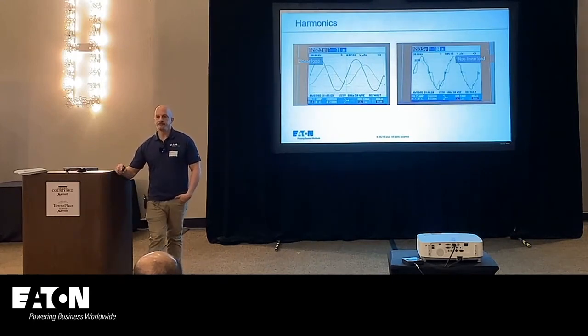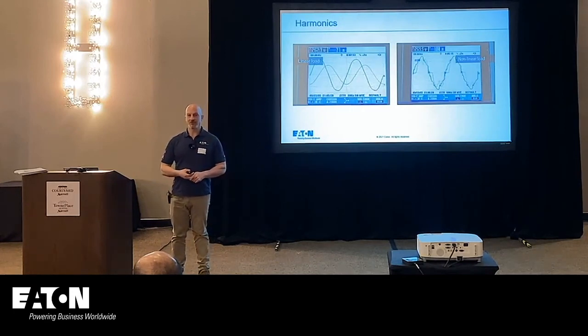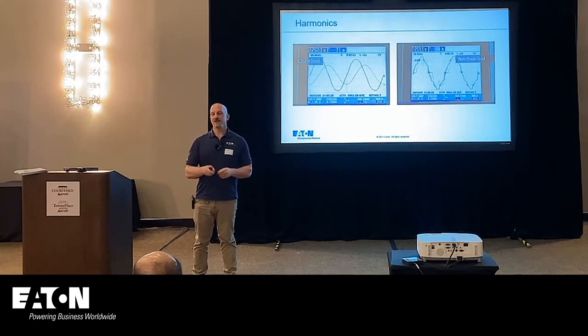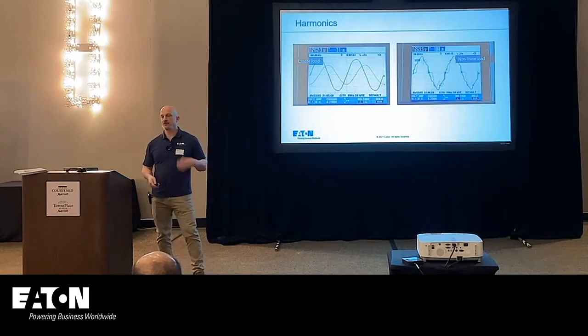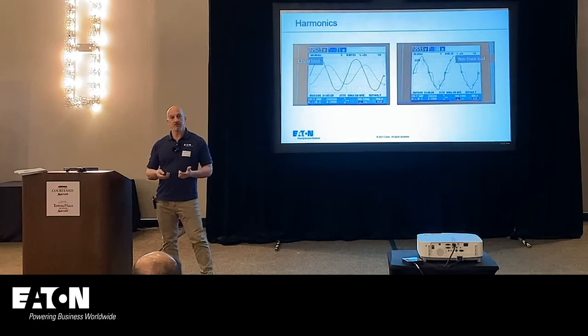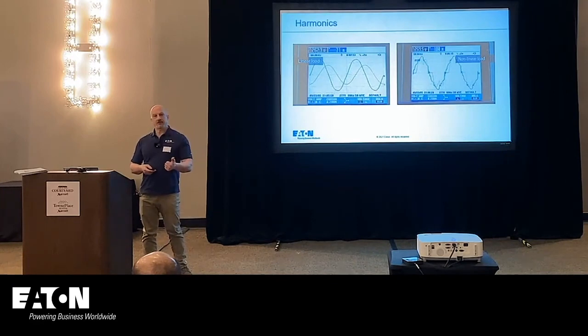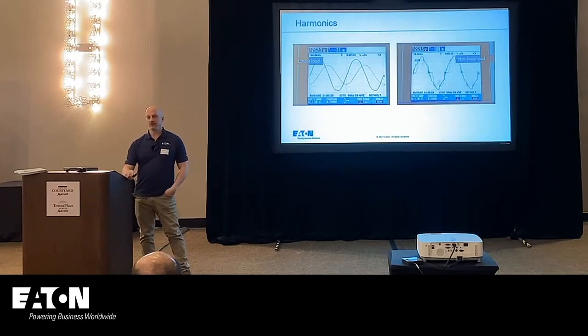But what kind of current is that one, that double hump current? Where does that come from? VFDs. And what type of VFDs, to give you another question, 6 pulse, 12 pulse, 24 pulse? 6 pulse. And what are the harmonics associated with 6 pulse drives? 5 and 7. So you took 6 plus or minus 1, and then 2 times that, 12 plus or minus 1, 11th and 13th. We'll come to that. But harmonics are predictable. That's the good thing. We know they're predictable, and they're characteristic of certain specific loads. So this projector has specific harmonics, drives have specific harmonics, other rectifiers have specific harmonics, and we can predict that, and then we can decide what to do with it, okay?